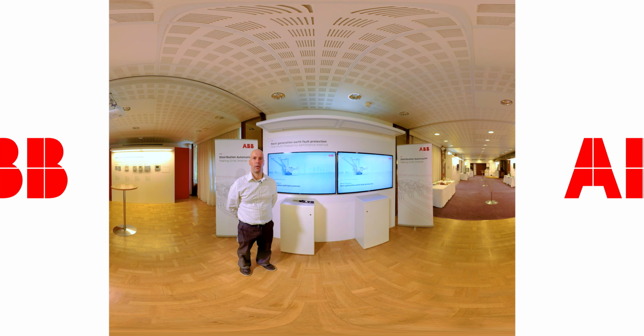I work as a senior principal engineer here in the relay factory located in Vaasa, Finland. In this next presentation, I will give you details about our latest earth fault protection functionality applicable in compensated networks. This protection function is called multifrequency admittance protection, and this is the latest protection functionality we have available in our Relion series of protection relays.